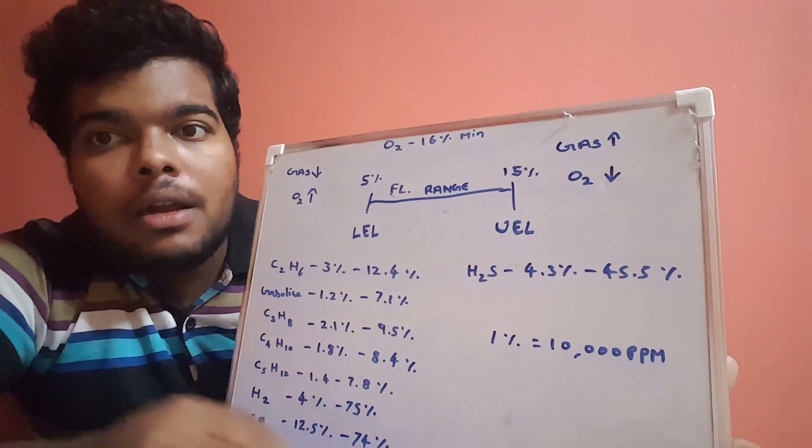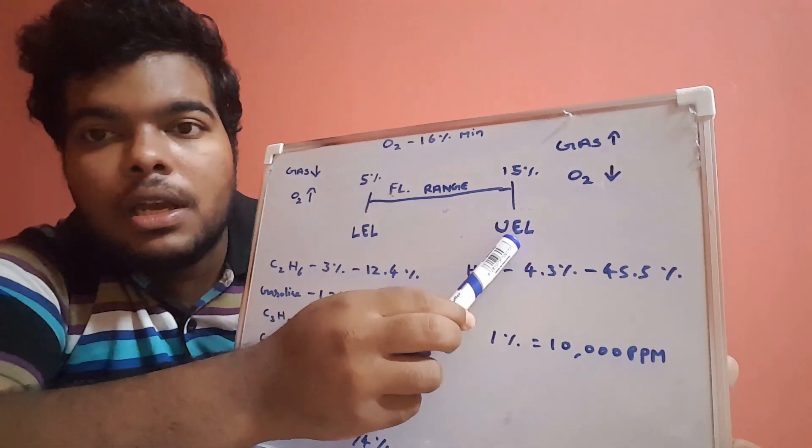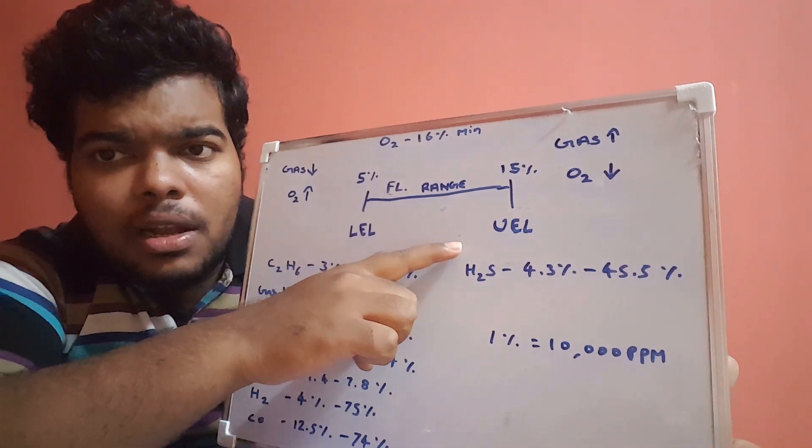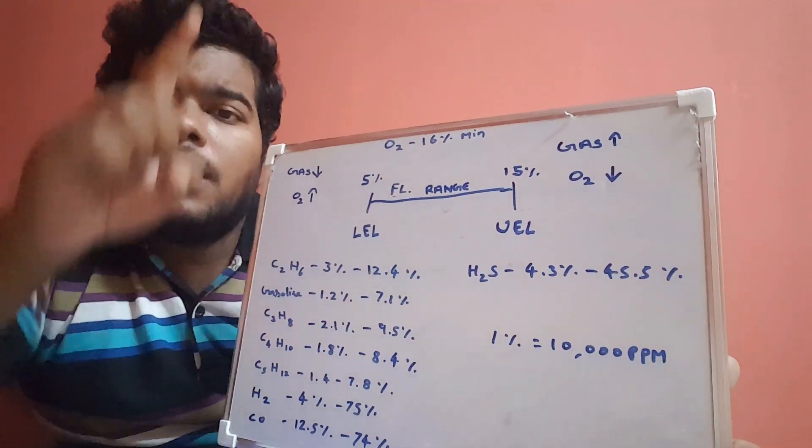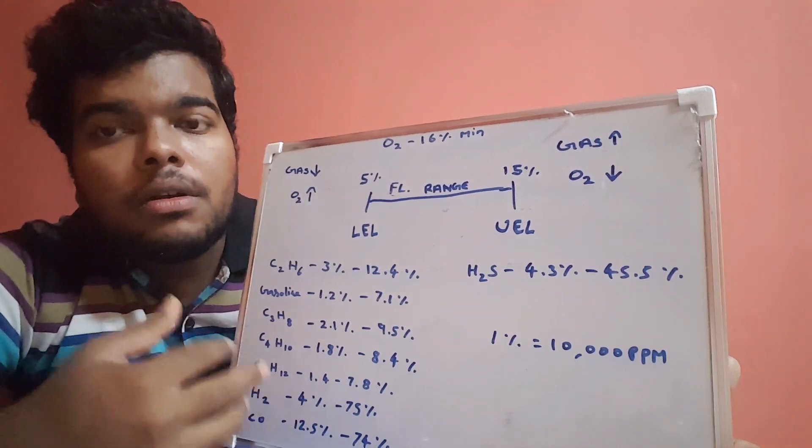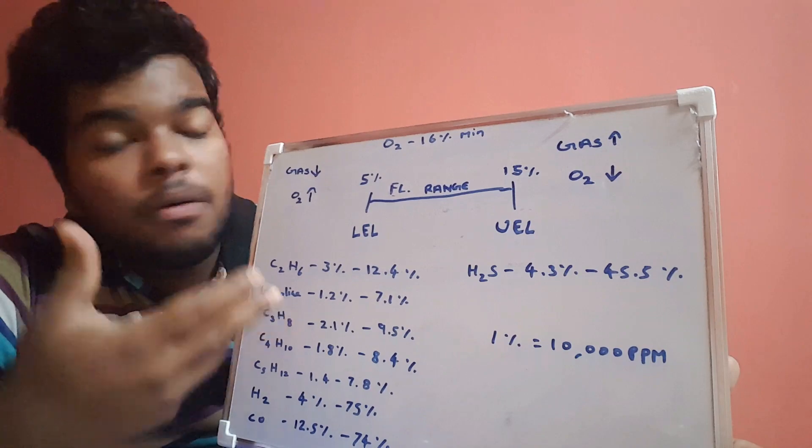To detect this UEL, definitely we need a detector which will work on low oxygen environment as well. Our multi-gas detector is only capable when the air is good and the oxygen value is in perfect amount.